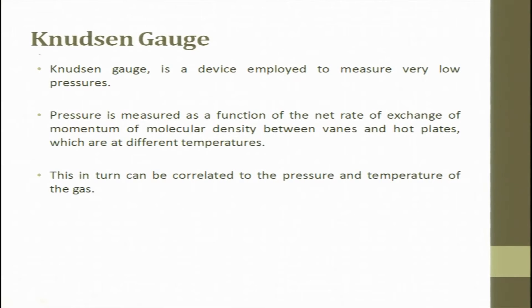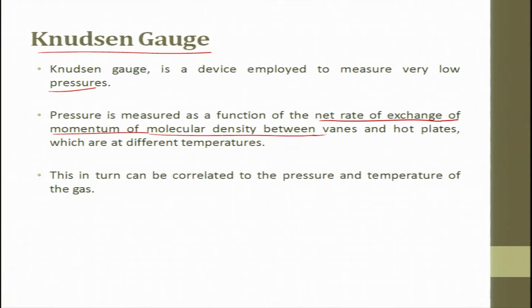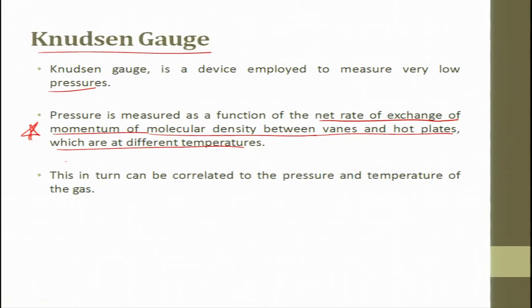Another gauge is called the Knudsen gauge; it is a device employed to measure very low pressure. The pressure measured is a function of the net rate of exchange of momentum of molecular density between the vane and the hot plate, which are at different temperatures. This is the principle with which the Knudsen gauge works — the pressure is measured as a function of net rate of exchange of momentum between the vanes and the hot plate kept at different temperatures, which in turn correlates the pressure and temperature of the gas.